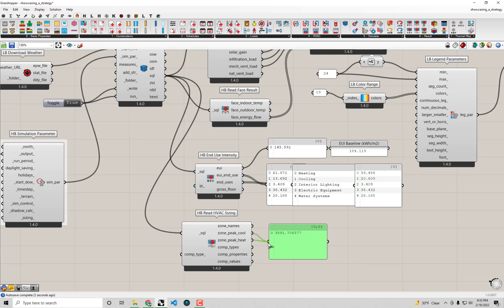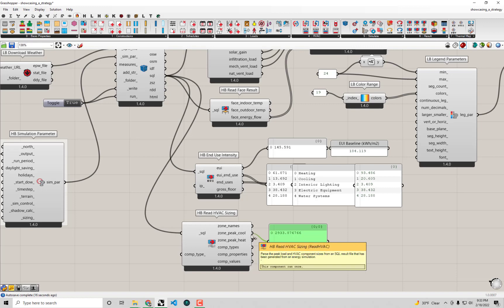If we hover over the zone peak cool output here, it tells us the peak cooling of the zone on the summer design day, and this value is in watts. Essentially, this is the amount of watts that need to be removed from the space in the hottest, sunniest day of the summer in order to ensure the thermostat can still reach the set point to make people comfortable.